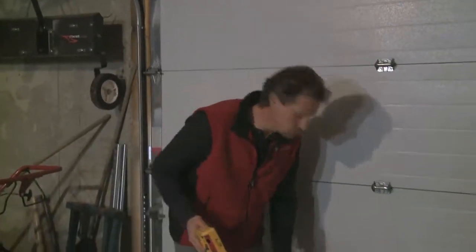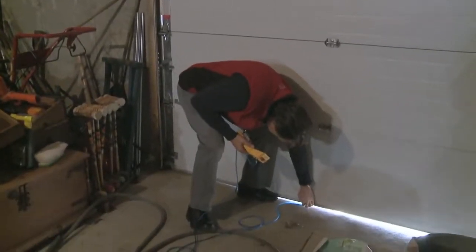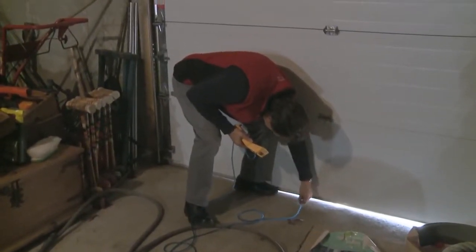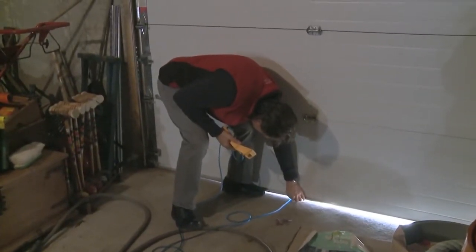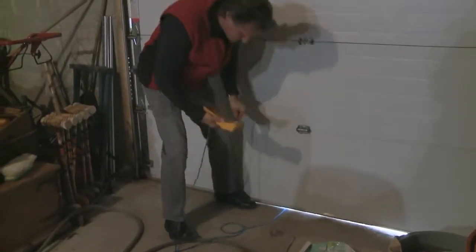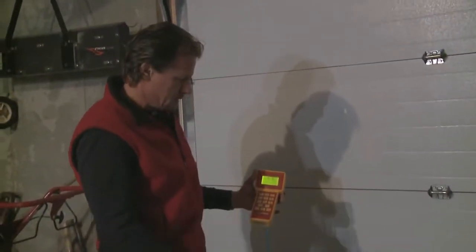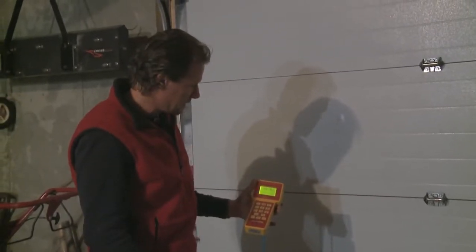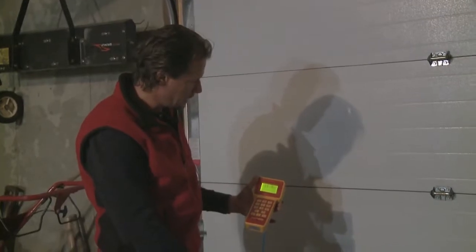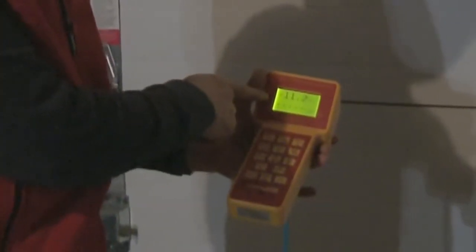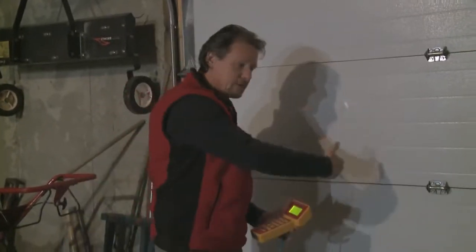This house is a little unusual, and it has a garage door in the basement. And so we have air leakage around the garage door, but that should reduce the negative pressure in the basement. So it's not giving us a false test, but we can see at the very lowest part of this house, very lowest, right along the basement floor, we have 11 pascals difference, negative 11 inside compared to outside.